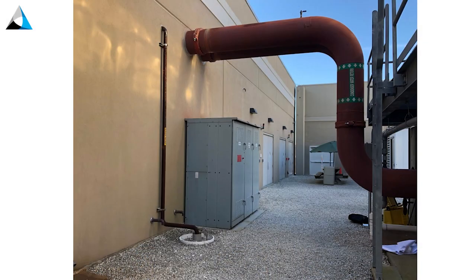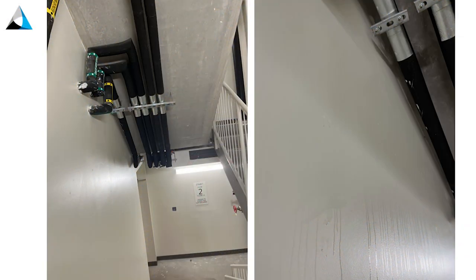Some things I like to take pictures of that just confound me on projects. You're not allowed to run things over piping or over switchgear or panelboards. A design review can help advocate for space — like for an IT rack so you don't have to put it not only in the mechanical room but below dripping pipes. In a stairwell, a fan coil unit was placed at the second level of a three-story building — not only is the piping ugly, but there's condensation at the upper levels. A design review might have helped.